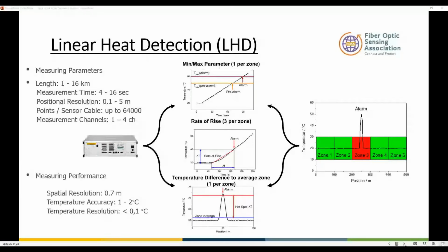What distributed fiber optic sensing provides in the linear heat detection mode is, because of its distributed nature, continuous temperature monitoring along the whole length of the fiber cable. That's a big one—there are no physical zones you have to engineer. You don't have to set up a zone physically; it's all set up in the software.